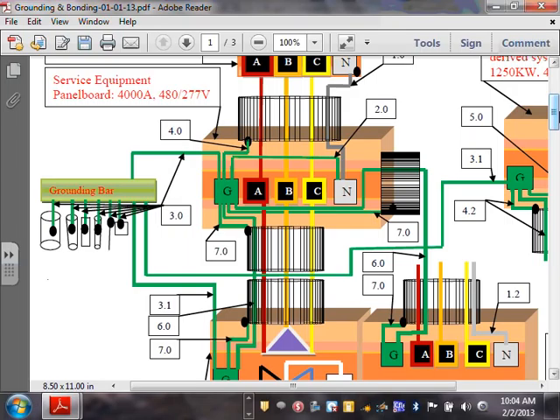So you have to put on your PPE and work on it. Do you really want to go torque anything here, and if you torque this one, you're going to work on it hot? So that's an advantage of having everything outdoors. Because they are now not hot, you can torque them, work on them, and inspect them without being dressed up in category 4 in this switchgear. Any comments, guys, about this? Any comments? You guys are all familiar with that one. Now, that's my neutral.